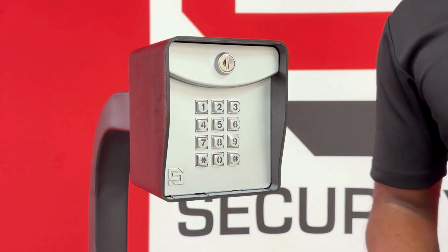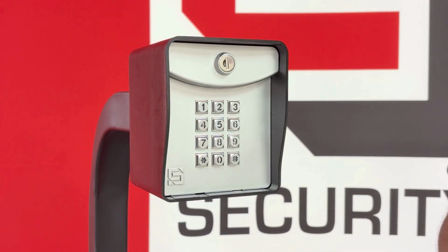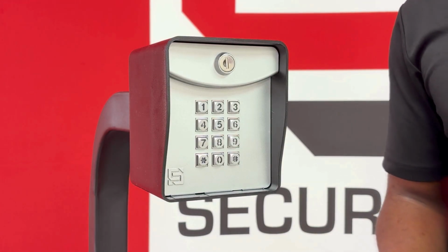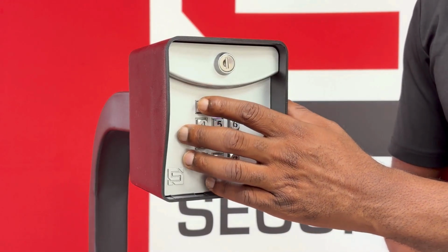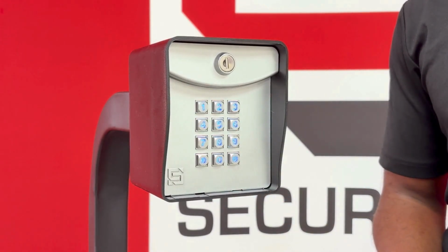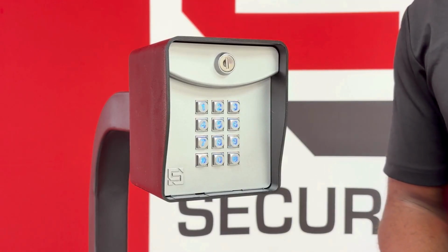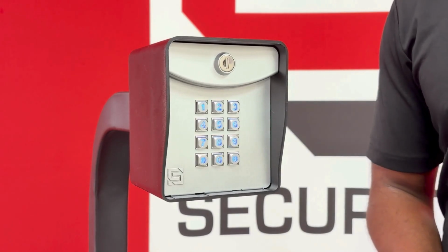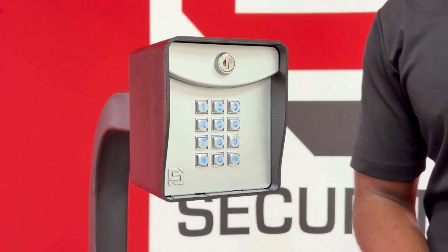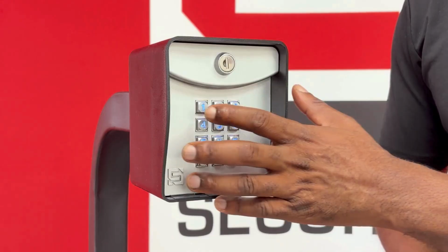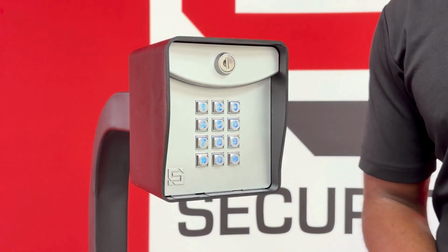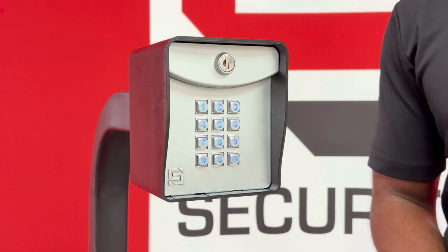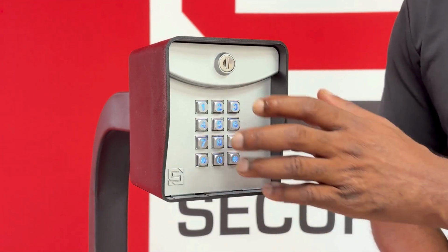Next, we're going to go ahead and add a latch code. We're going to start off by using our default master code, which is going to be 1251. Then we're going to enter the submode for adding that hold open or latch code, which is submode 5. Then we're going to select the channel that we want to use, which is going to be channel A. So we'll hit 1. And then we'll add the code that we want, which in this example will be 2525.